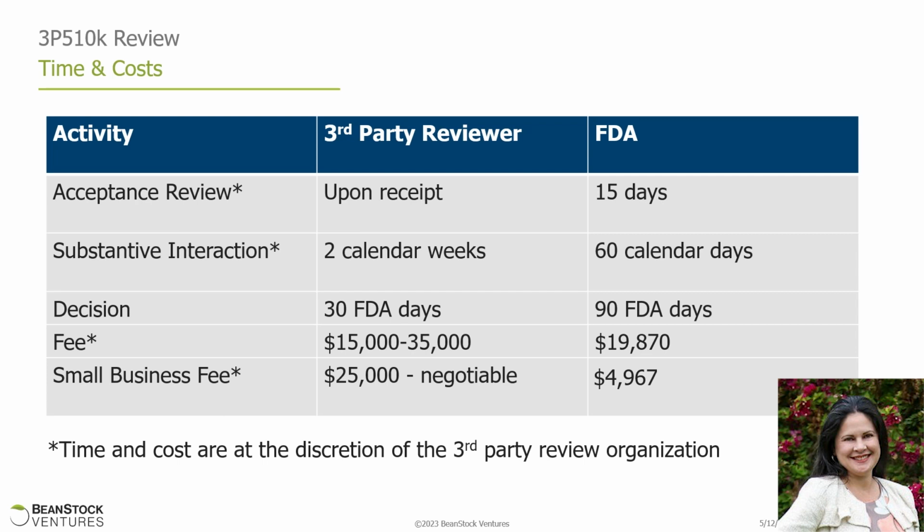FDA, if you go direct to the FDA, that's a 90-day commitment. The fees, they're pretty comparable. So from a third-party review organization, we've seen fees range anywhere from 15 to 35K. The upper end of the range really depends on the complexity of the device and whether or not there's additional special controls to be considered.